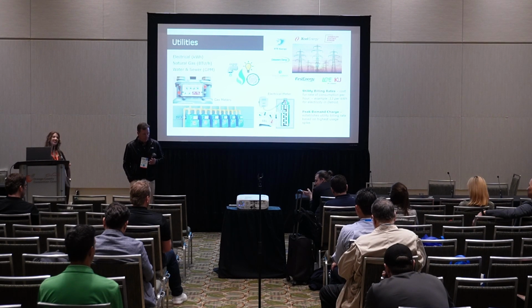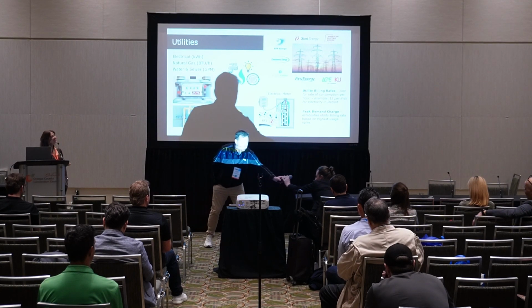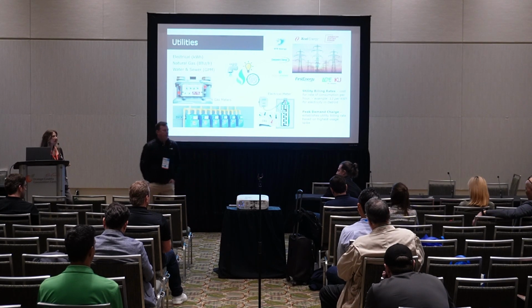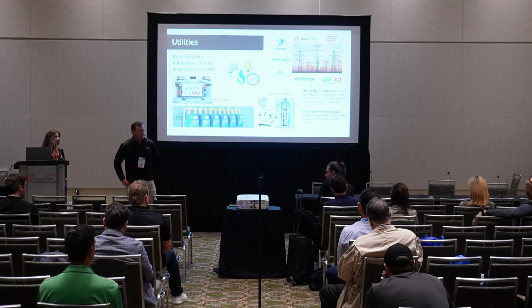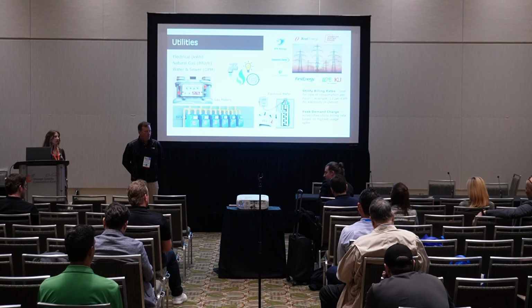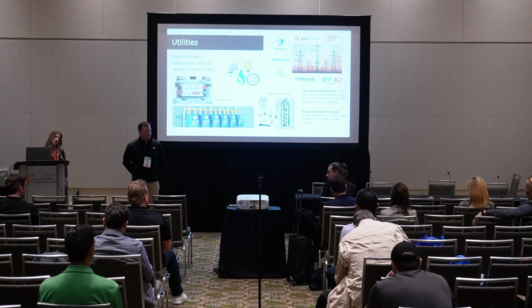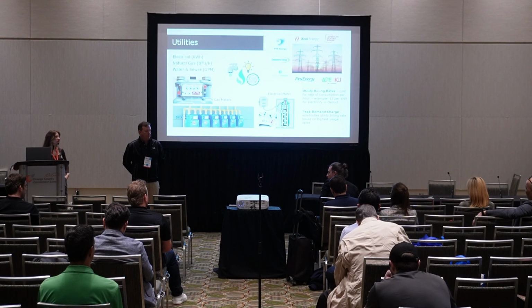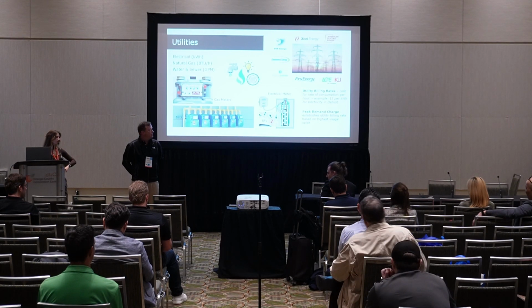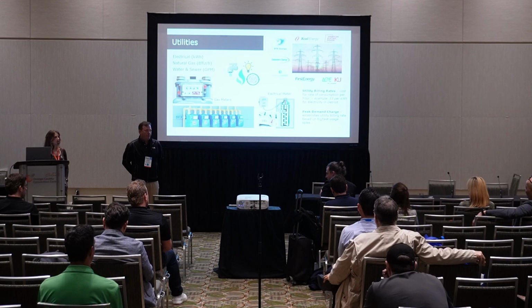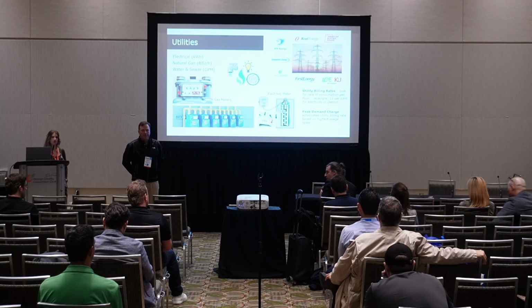Thanks Scott, I was just going to say the set point relaxing thing, I think in theory is a good idea, but in practice it's slow. It takes a while to actually lower the peak. So what I found is it's actually less effective than just going into a speed drive and taking 10 or 20% off that speed drive set point, which we've done.